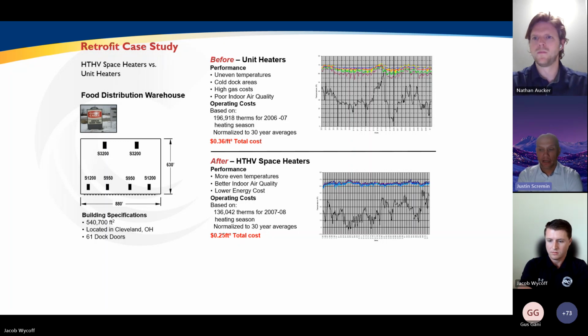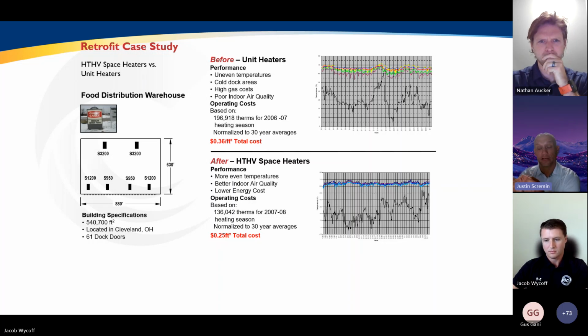Now, 99 times out of 100, when we look at our BTUs and then look back at how many CFM it's going to take to move those BTUs, we meet our ventilation calculation. So the majority of the time, unless you're using something else besides a high bay warehouse type application, you're not going to need an additional makeup air unit. This unit will actually function as the heater, that's its primary function. It will function as the makeup air unit, so it'll introduce the ventilation air, but it will also do destratification. So it's really taking care of 3 different pieces of equipment.